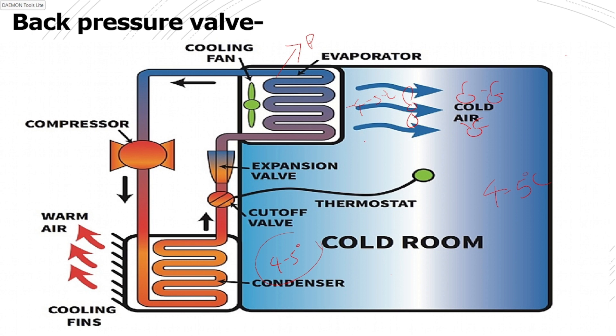So how to avoid that? You can define a minimum temperature for the air blown over the vegetables coming out from the evaporator. The back pressure valve sets this limit — it limits the saturation temperature of the refrigerant to 0 degrees or a higher value, wherever you want to maintain the cool room temperature. The pressure is set to achieve that minimum 0 degree temperature coming out from the evaporator.